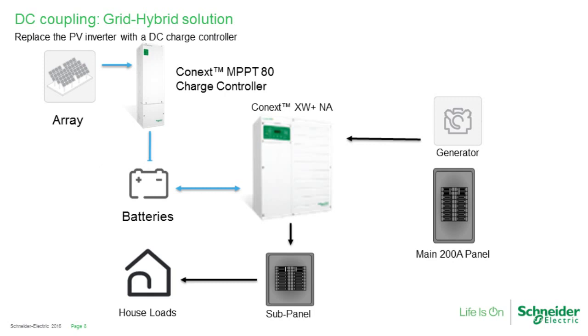Of course, when we lose power on the solution, that system is still going to be able to provide backup power to that sub panel and to those household loads. The really great thing about the XW Plus, of course, is it has dual AC inputs. So it can not only sell power back onto the main panel out to the grid, but if there's a generator already on site, then that system is going to be able to call on the generator to begin charging if the batteries can't keep up. And that can be in the middle of the day, actually.